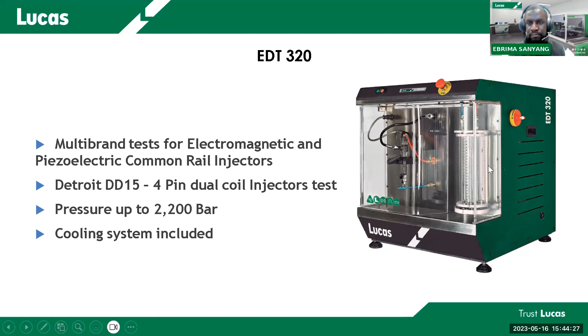So you don't have to enter the figures manually. In the 320, you have to type in the flow on each step, because as you can see here, the tubes are entered manually. The EDT 315 has digital flow meter reading, so you don't have to enter the flows, the system and software will do that for you. You just have to put the injector on.